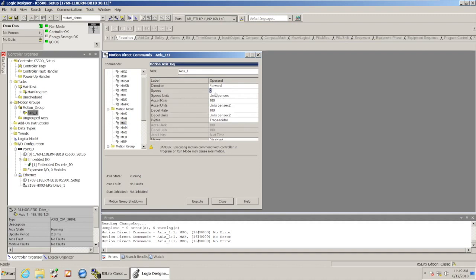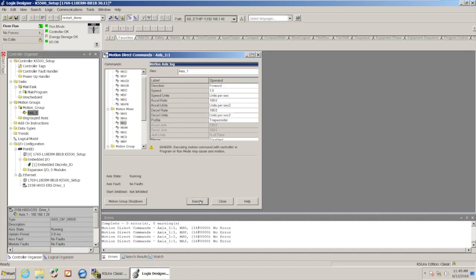So I'm going to issue a motion axis jog or an MAJ. I just have to add a speed in there. And again this is in units per second or revs per second is what we scaled to. You can also adjust the accel and decel rates. I'm going to leave those at the default for right now and just go ahead and execute this.